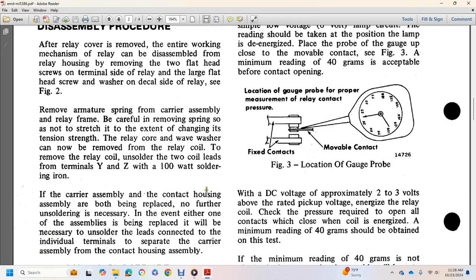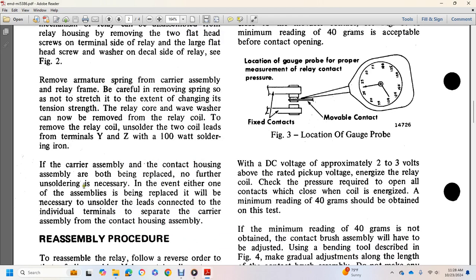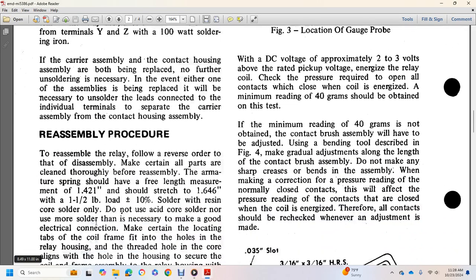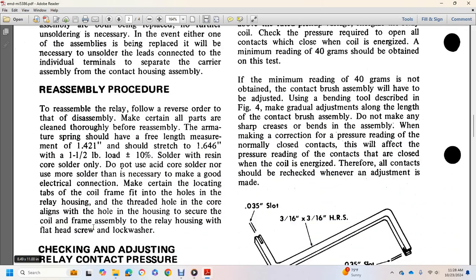If the carrier assembly and the contact housing assembly are both being replaced, no further unsoldering is necessary. In the event either one of the assemblies is being replaced. It will be necessary to unsolder the leads connected to the individual terminals to separate the carrier assembly from the contact housing assembly. Reassembly. Proceed with reassembly of the relay by following the reverse order of disassembly.